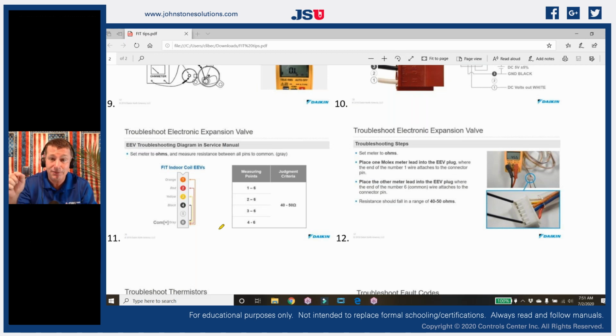And all it's doing is it's firing those coils in order: 1, 2, 3, 4. It's trying to move that piston all the way open so that it sees where its maximum open point is, and then it's going to go 4, 3, 2, 1, and keep going until it stops and meets a little bit of resistance, and it goes, oh, well, this is closed.